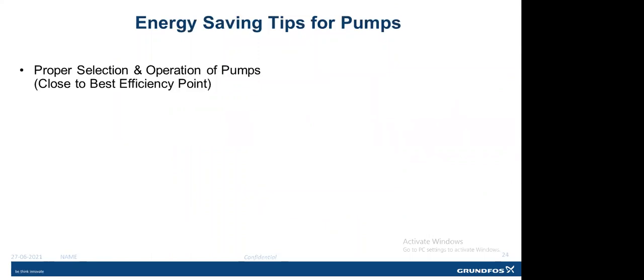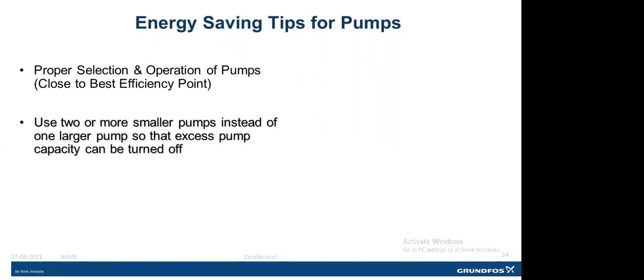So we'll discuss some common energy saving tips. First is proper selection and operation of the pump. Always select the pump close to the best efficiency point. Use two or more smaller pumps instead of one larger pump so that excess capacity pumps can be turned off.